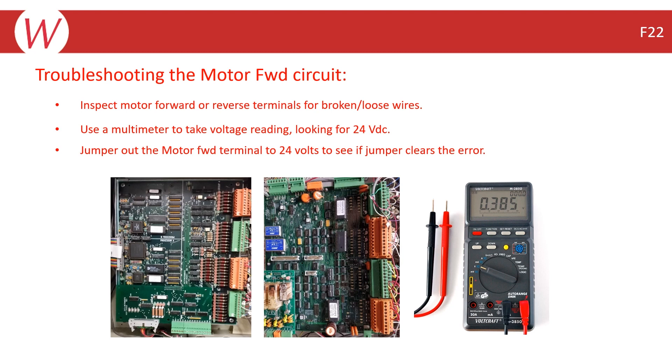If you are still not able to find the open connection, perhaps due to an intermittent connection that the meter is too slow to detect, you could jumper out the motor forward or reverse terminals to see if jumper clears the error. Remember, the indicator LEDs on the board can also be used to indicate whether the motor direction inputs are receiving the signal they need to be satisfied.